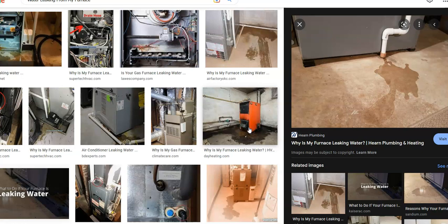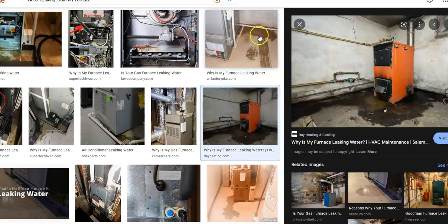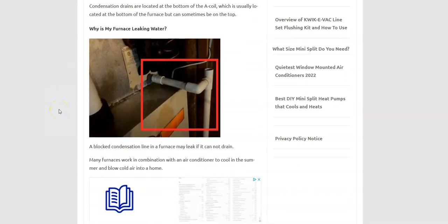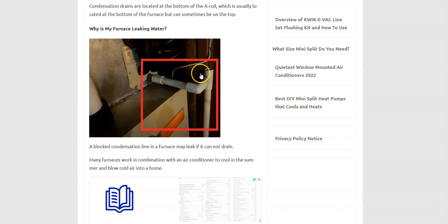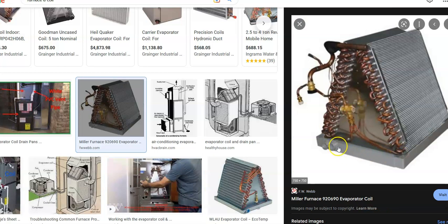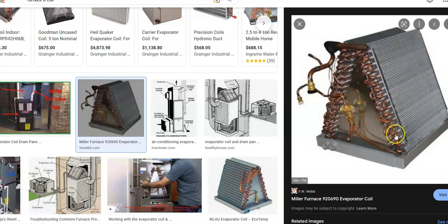When you're having this problem, you need to go examine the furnace and see why it may be leaking water. The first thing to do is to locate the A-coil and locate this drain line right here and see if it's just partially plugged up. It might not be hugely plugged up, but it might be really plugged up good and you might have to really get into it. One thing to mention is that quite often at the bottom of the A-coil, that pan, this pan down here, if they get debris built up inside of them, then that'll cause it to plug up.